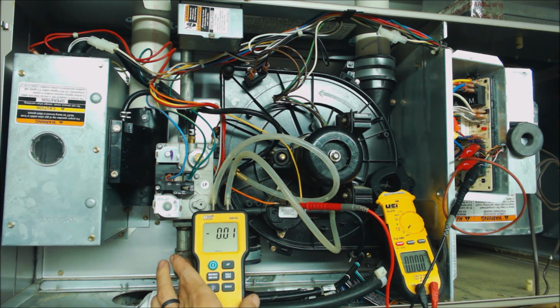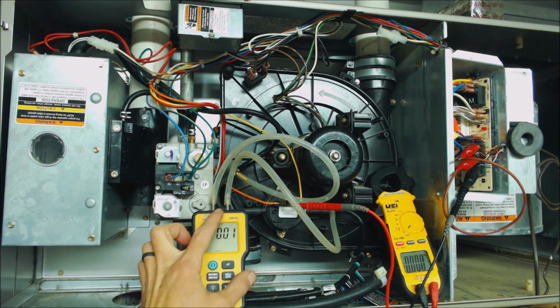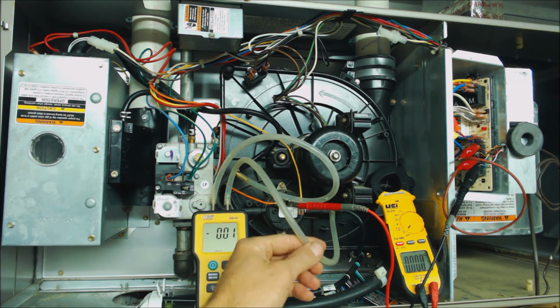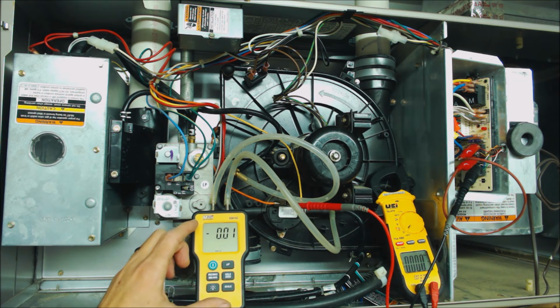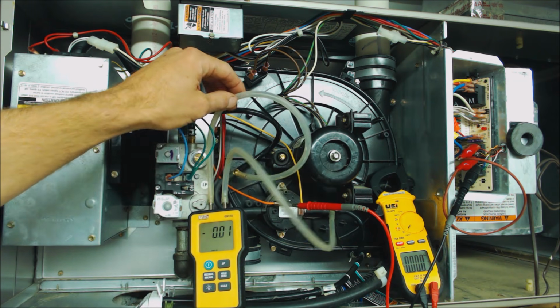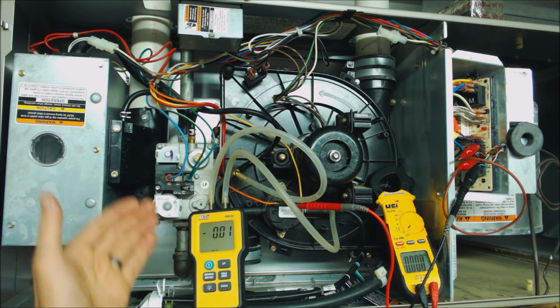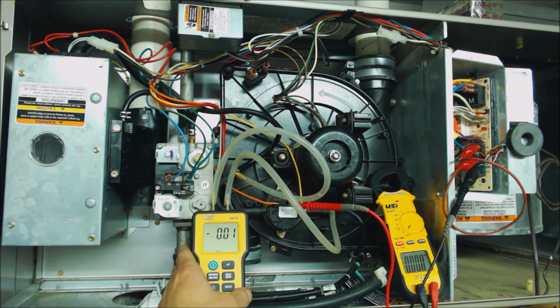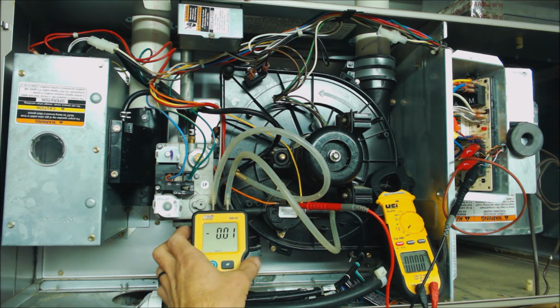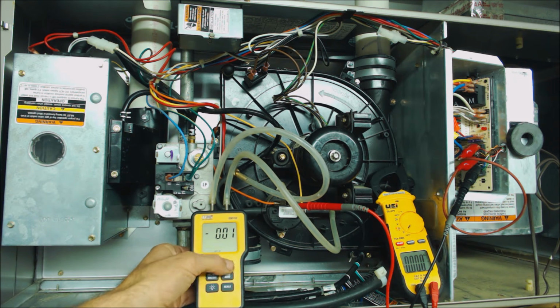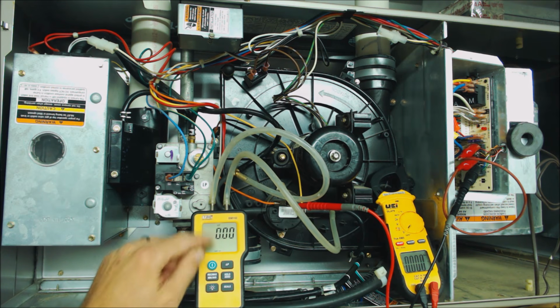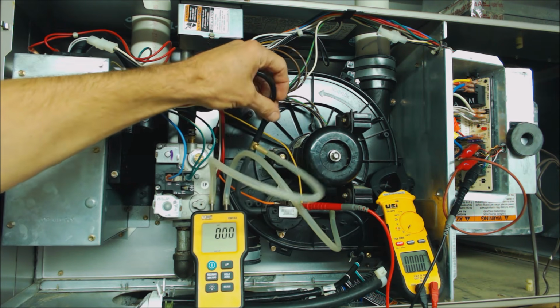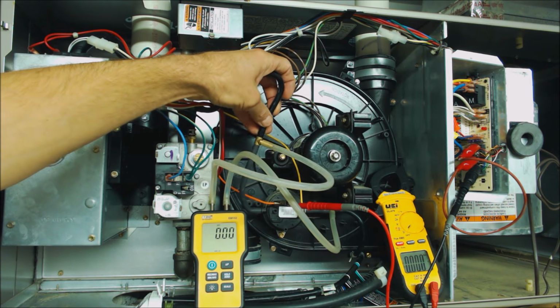So that's why we have to read it with a dual manometer, and we're going to read our negative side over here. And if there's a positive port on your dual manometer, you can attach it to this side. So once again, it's not a matter of positive or negative pressures, it's just that's how a differential would work. You would need a positive and a negative in order to come up with a differential. So we're going to press this, and we see DIFF. We're already zeroed out. I used these brass tees. I have them linked in the description below in order to tee in the water column manometer.